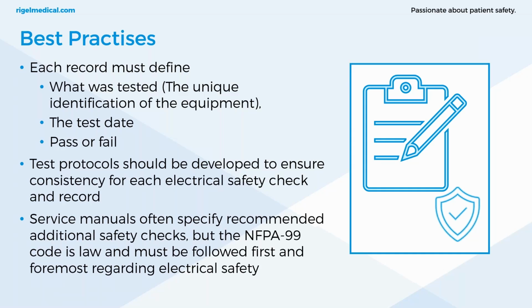Test protocols may have the electrical safety measurements. I mean, it will help if you ever have any legal issues or any problems with a medical device. If you've got recorded values, then it does help in some ways. But NFPA 99 only specifies these three things: the device that was tested, so the unique identification code, the date that it was tested, and whether it passed or failed. It's quite simple. At the very minimum, these are the requirements.